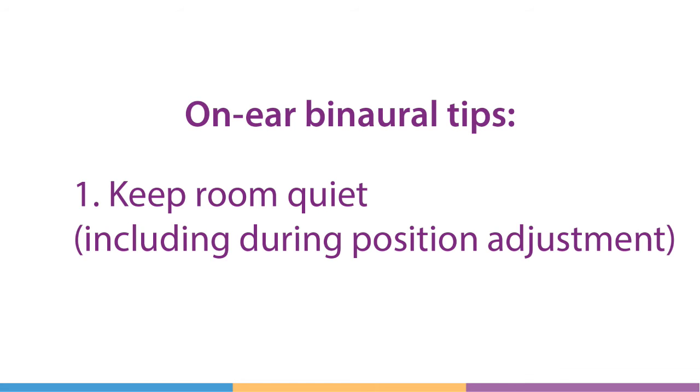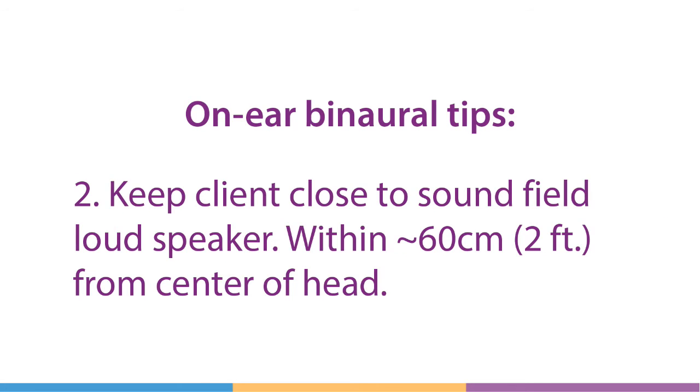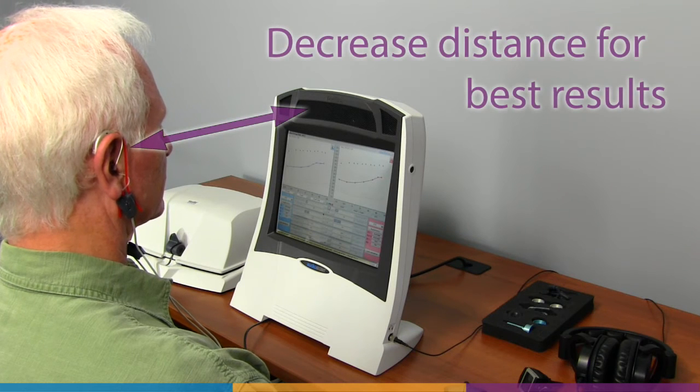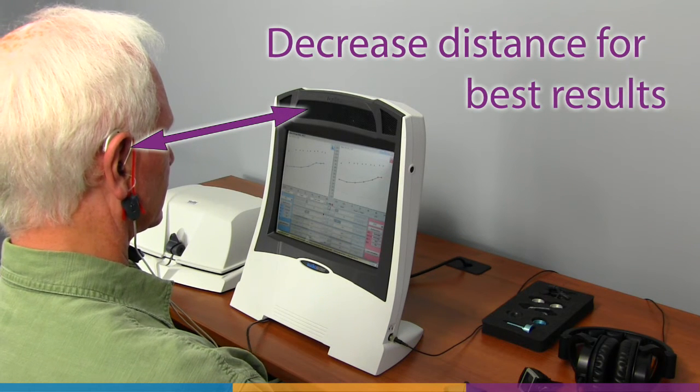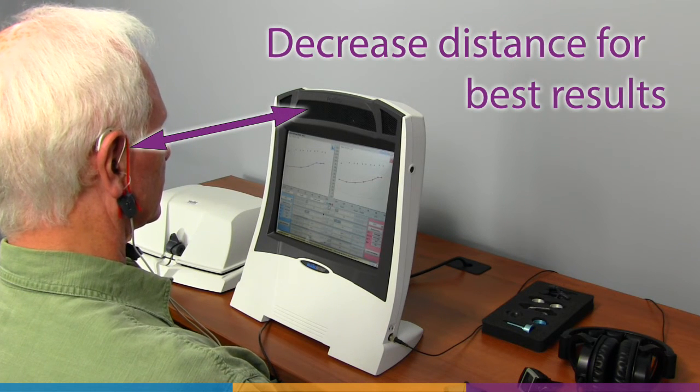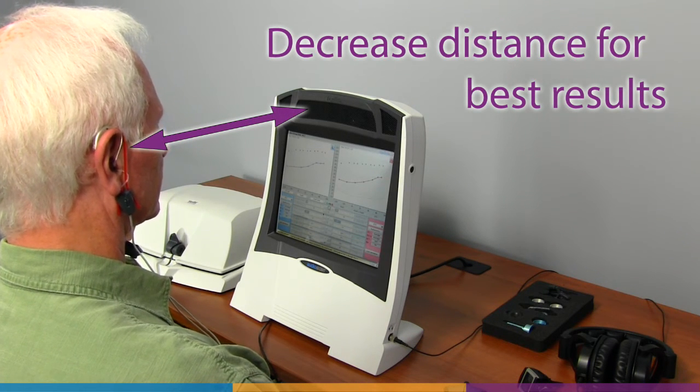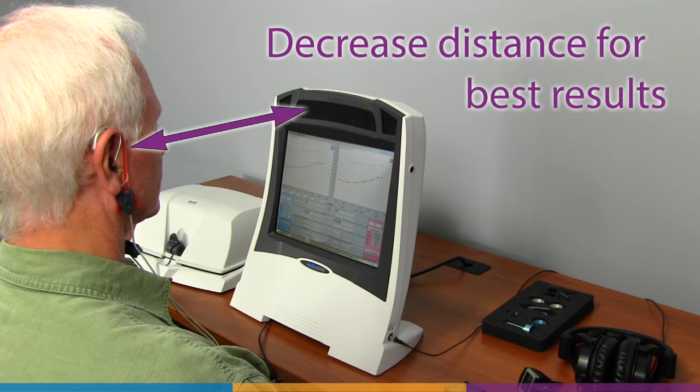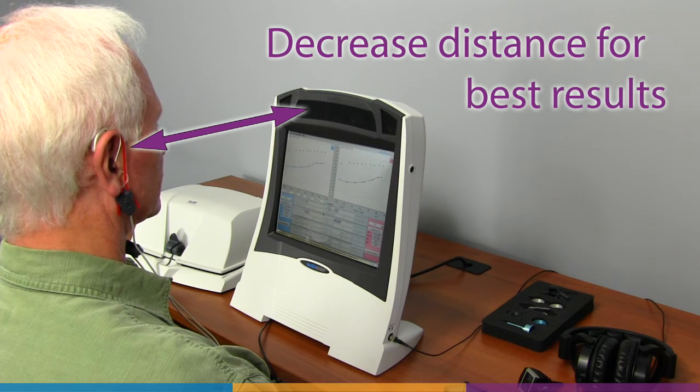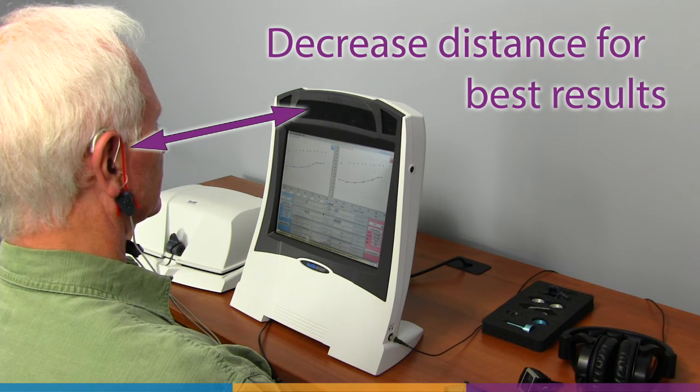As with all real ear measurements, best results are obtained in a quiet environment. This concept holds true during the position adjustment step. For reliable use of binaural sound field assist, we recommend the sound field speaker be no more than 60 centimeters or two feet from the client's head at zero degrees azimuth and away from reflective surfaces. Consult the user guide for optimal room setup guidance.